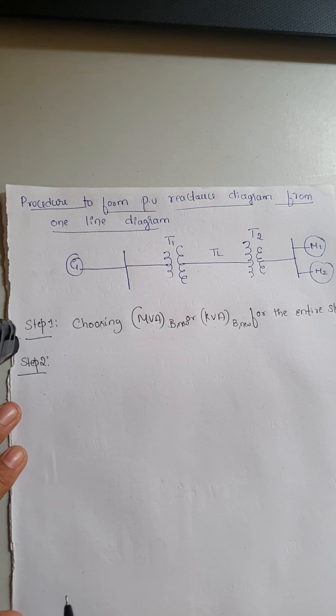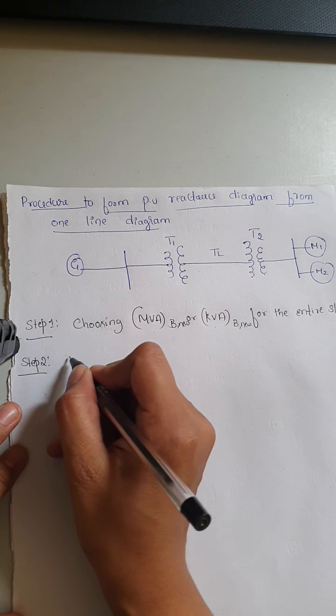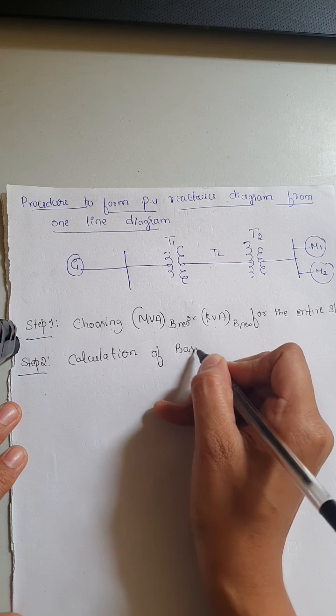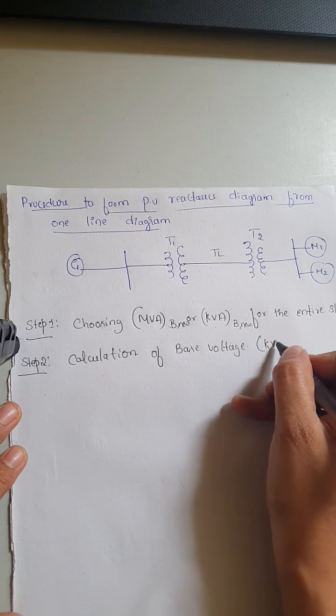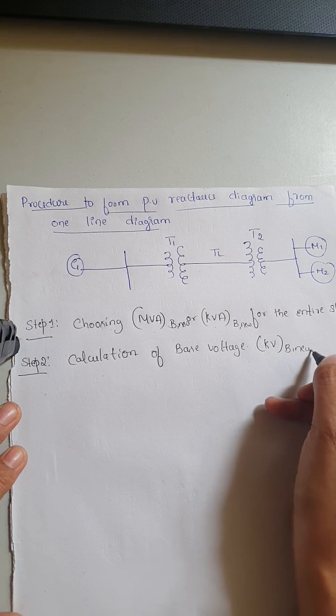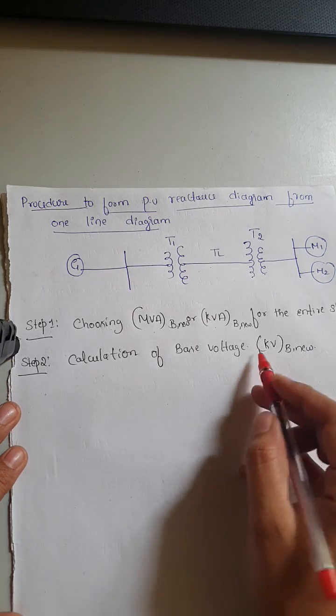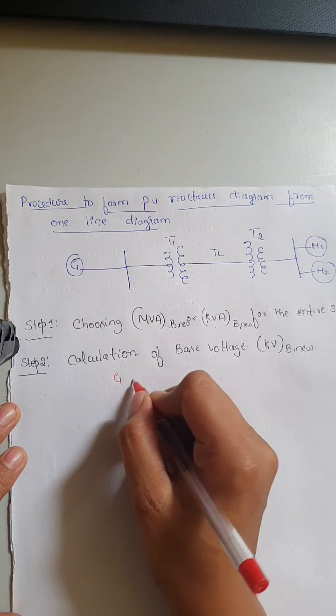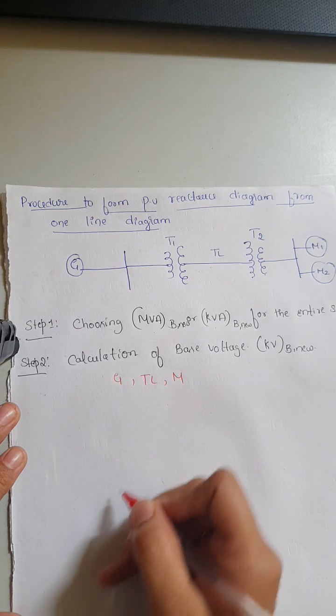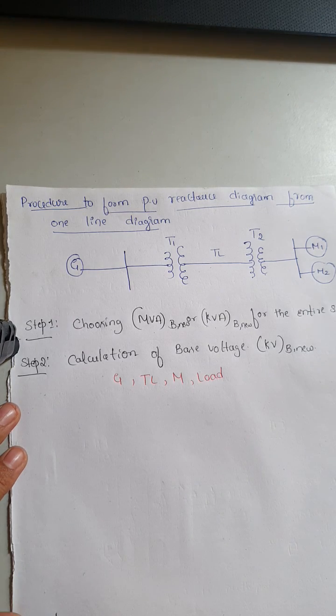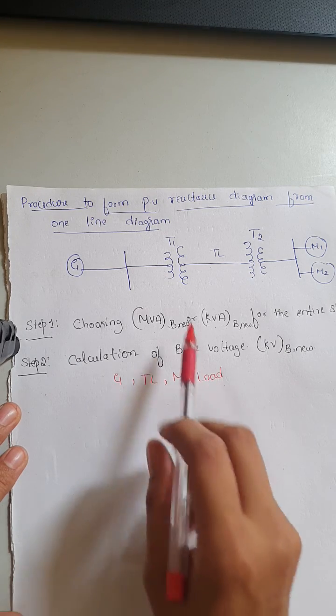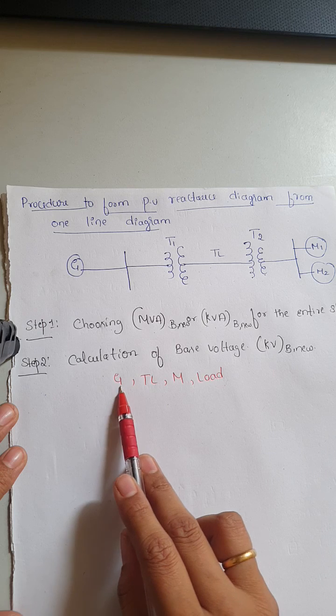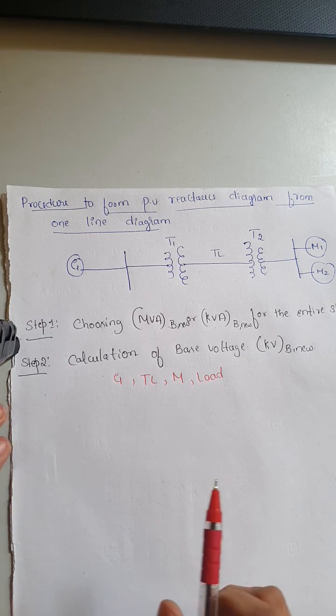Step two is the calculation of base voltage. Here you calculate the KV base new for selected components in the single-line diagram. You are going to calculate base voltage for the generator, the transmission line, the motor, and if a load is present, for the load as well. Before applying the formula, we need to differentiate which components are on the high voltage section and which are on the low voltage section.